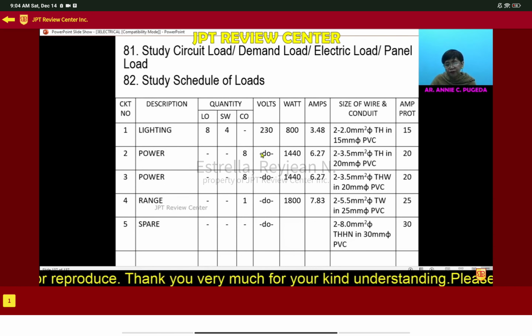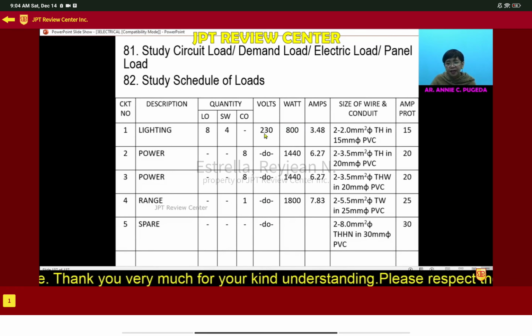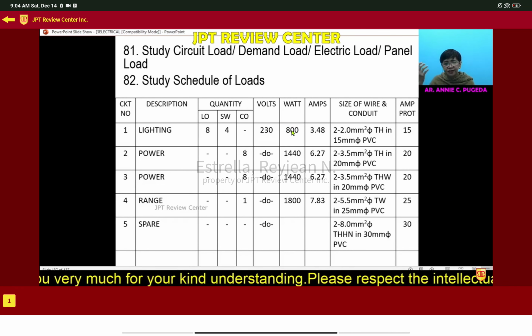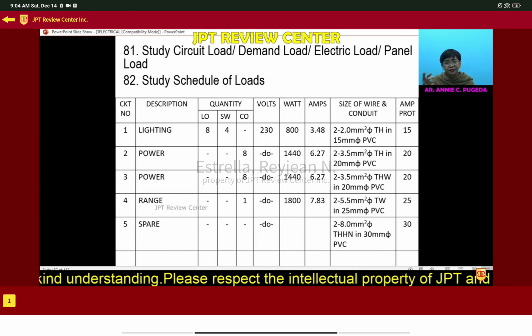230 volts ang binibigay ng power utility company, and the rated wattage is seen on the table. For example, if I have one lighting outlet, it is rated 100 watts per lighting outlet. So do the math: 8 times 100 is 800.